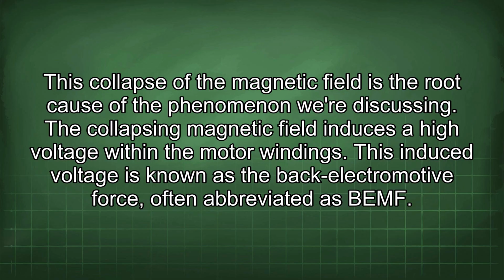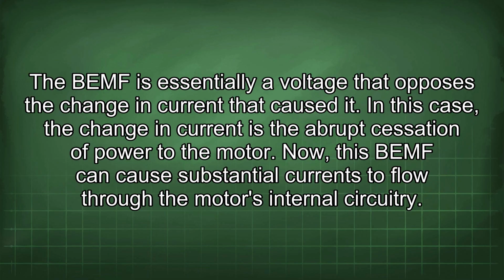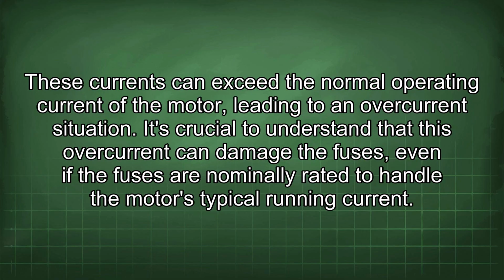The collapsing magnetic field induces a high voltage within the motor windings. This induced voltage is known as the back-electromotive force, often abbreviated as BEMF. The BEMF is essentially a voltage that opposes the change in current that caused it. In this case, the change in current is the abrupt cessation of power to the motor. Now, this BEMF can cause substantial currents to flow through the motor's internal circuitry. These currents can exceed the normal operating current of the motor, leading to an overcurrent situation.